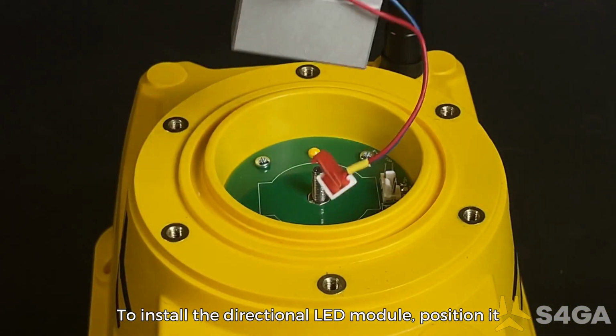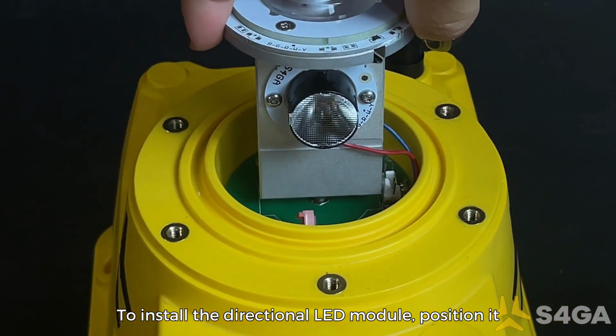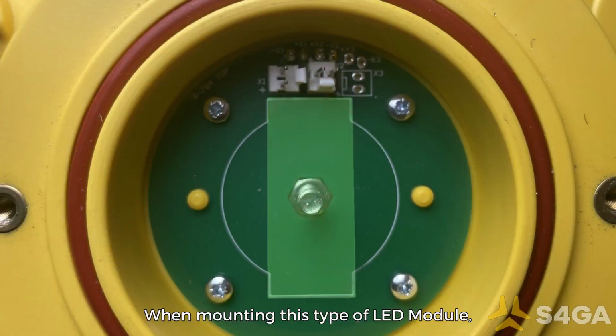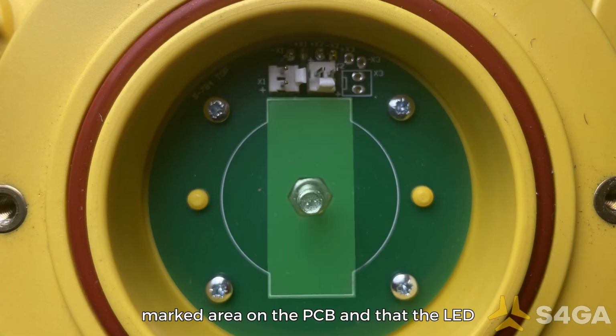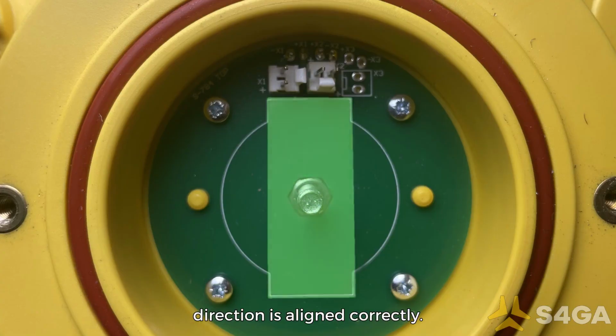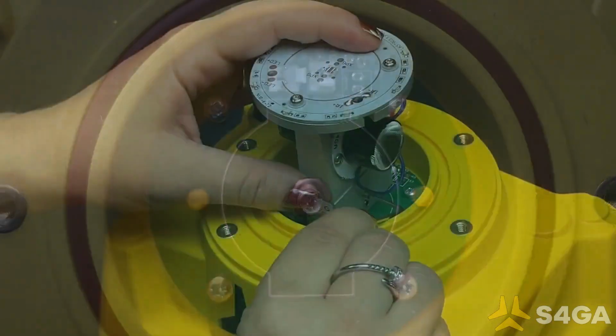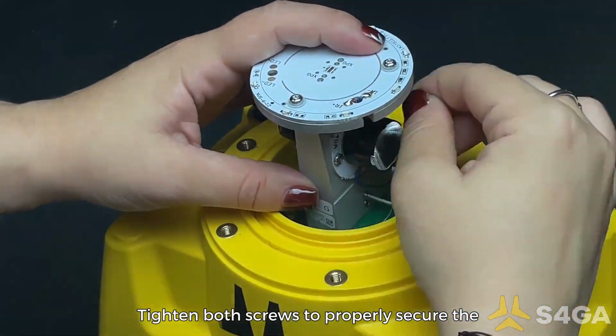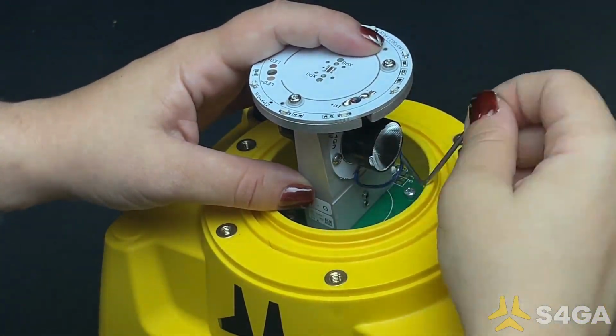To install the directional LED module, position it onto the protruding bolt. When mounting this type of LED module, ensure that it is positioned within the marked area on the PCB and that the LED direction is aligned correctly. Tighten both screws to properly secure the LED module.